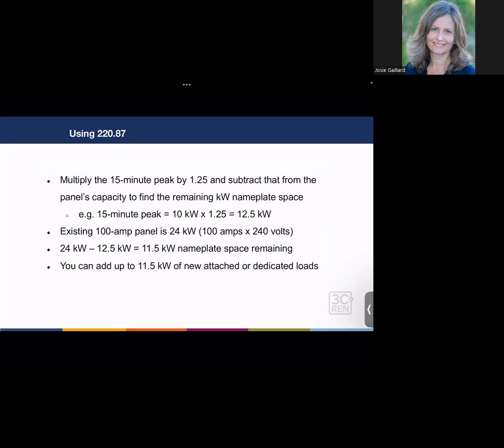So then we take that 15-minute peak, multiply it by 1.25, and let's just assume they had a 10 kilowatt peak instead of what we just saw, which was 4. 10 kilowatts times 1.25, and we get 12.5 kilowatt peak for a home. So we can assume that the existing power capacity for the home, if it's a 100 amp panel, is 100 amps times 240 volts, 24 kilowatts. So now let's just do some easy math here. 24 kilowatts, which is the max capacity of the panel and service line connection for that home, minus the peak that we've observed over the past year, which was 12.5 kW, and you get total available space for new appliances of 11.5 kilowatts.